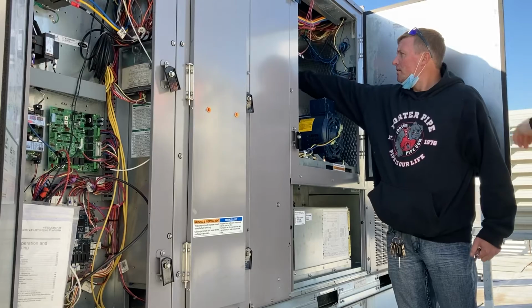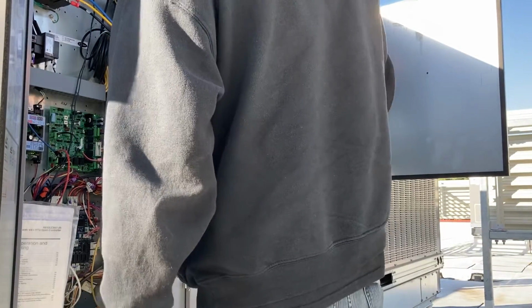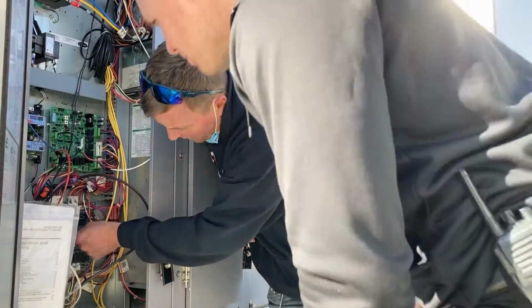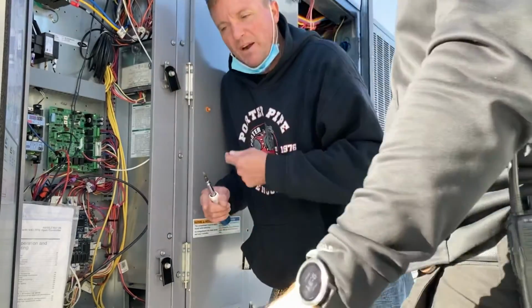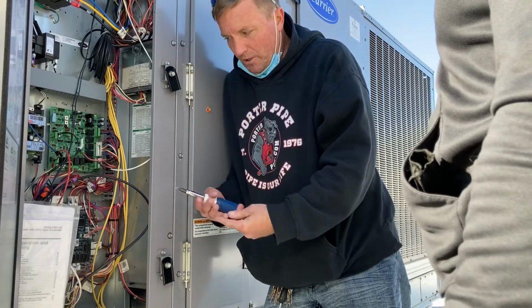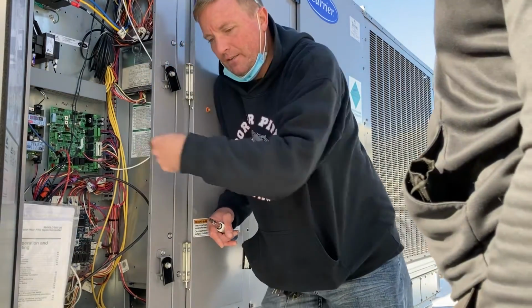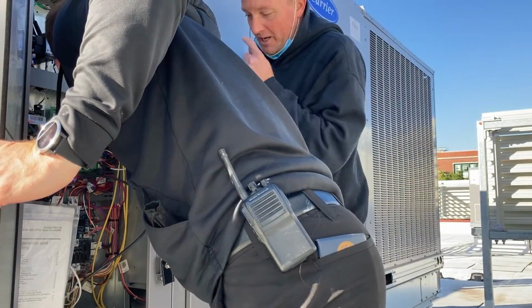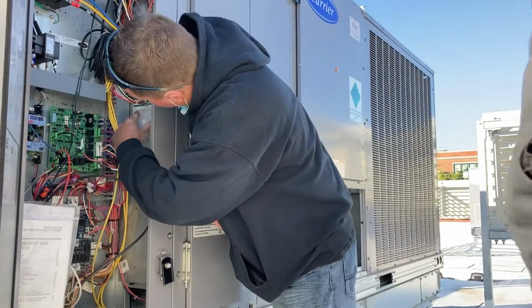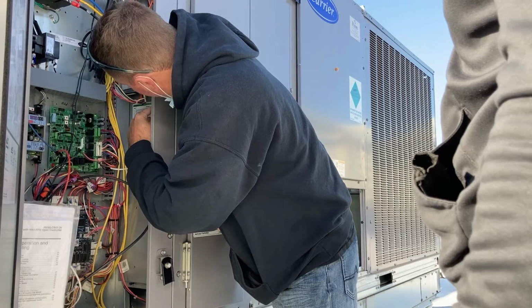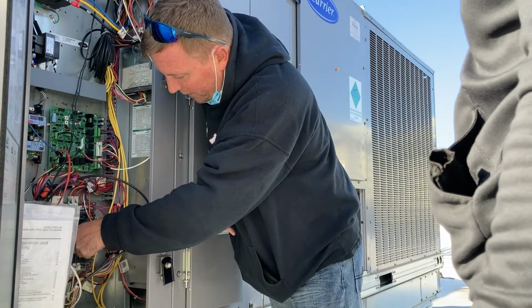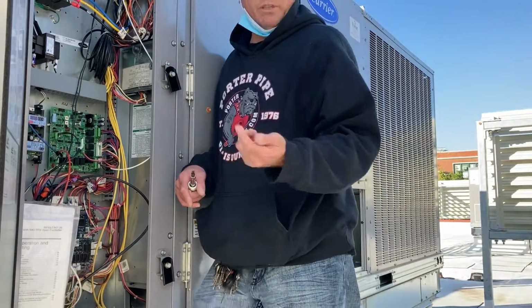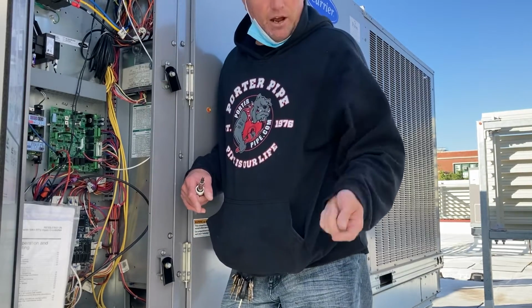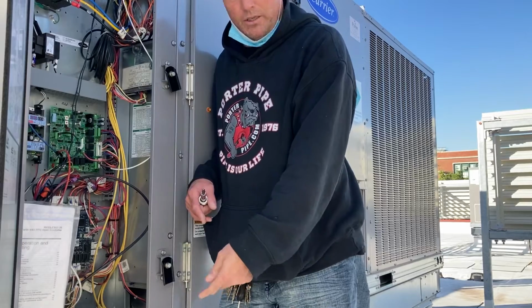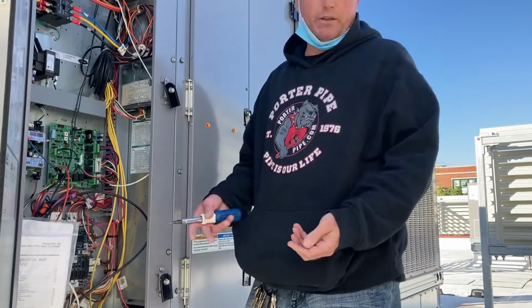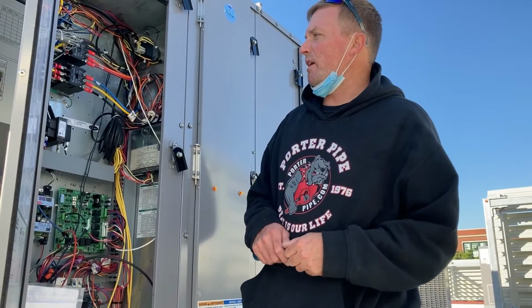Smoke alarm here, okay? If you have a smoke trip, or any kind of alarm, come on over to the side. The board down here has 5 LEDs. High pressure, low pressure, whatever pressure, if something in the BAS isn't picking it up and you come up to the unit, you'll get a flash code. Right here on the side is your 5 LEDs. You just find what the flash code is. Like I said, if it was a smoke trip, we'd get this smoke remote trip, and it would be LED 1 off, 2 red, 3 green. So 3 would be blinking and 2 would be on, and we would just look at the nomenclature on this and it would tell us what the alarm is. So at the end of the day, BAS or not, if the unit's down because of an internal alarm, you can always look here. No matter what, you have a way to at least diagnose it. At that point, we can do our normal troubleshooting and figure out what's wrong with it.